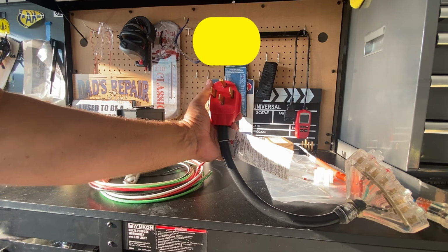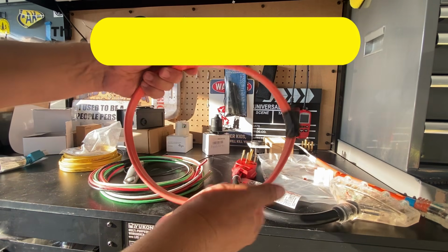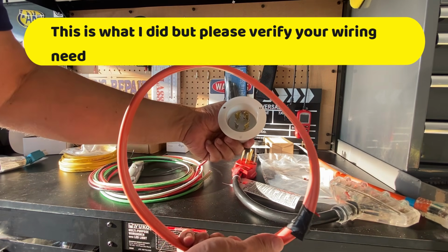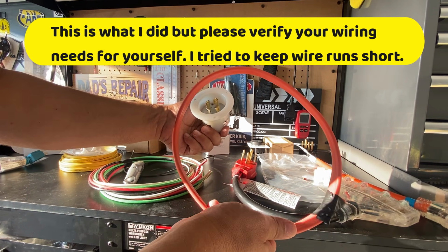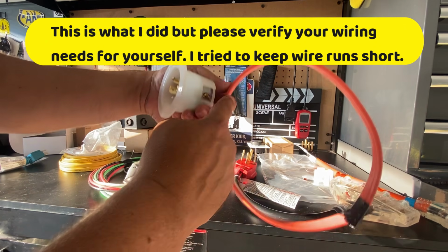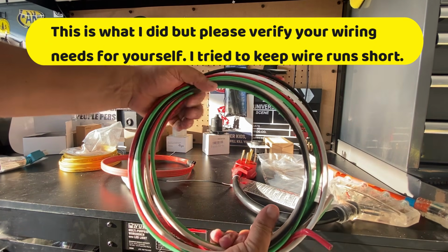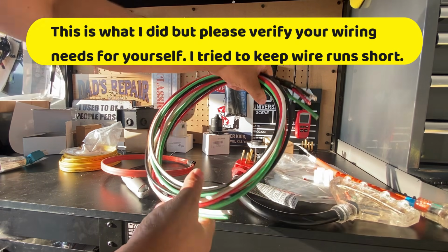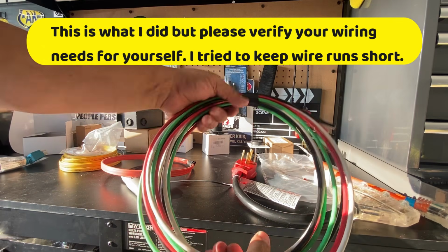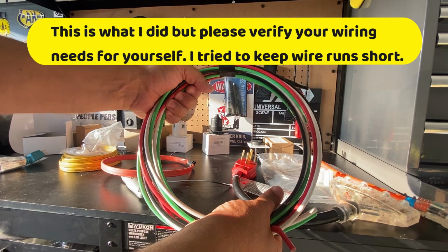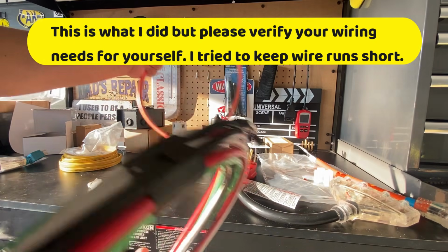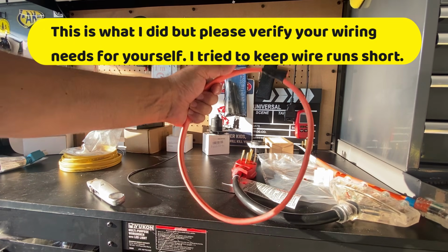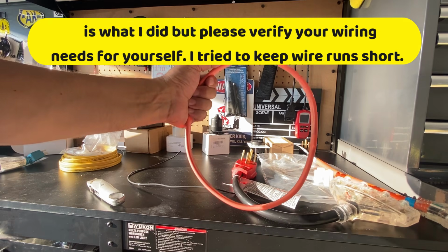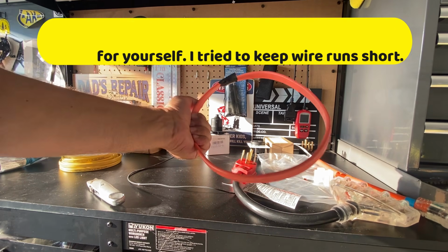As far as wiring, for the 50 amp I installed 6-3 cable in Romex. For the 30 amp plug, I used 8-3. You want to use this one right here with this sheathing, not this cable. These individual cables cannot be freely run behind the wall, they need to be run inside approved conduit. So this is super complicated, and this is very easy to do. As a pro tip, if you want to save money on wire, buy it by the foot. For my job I used about 5 feet and still have 2 feet left.